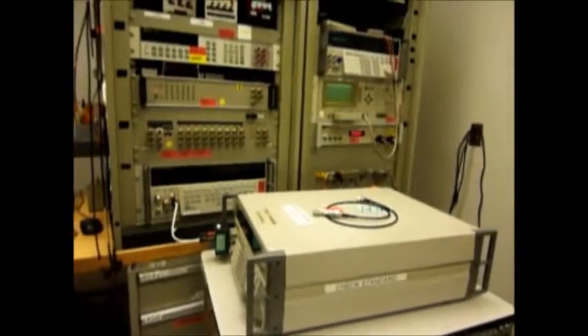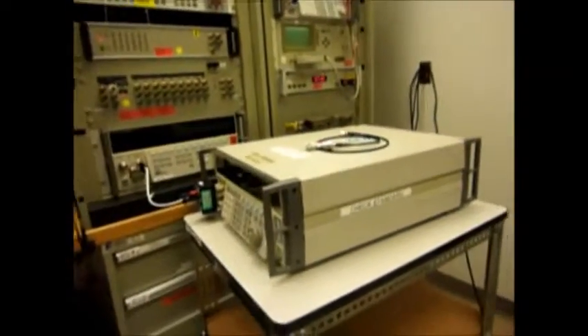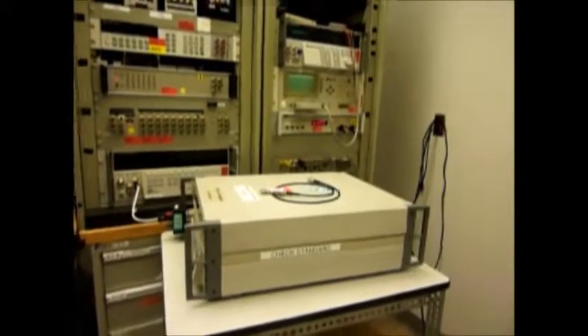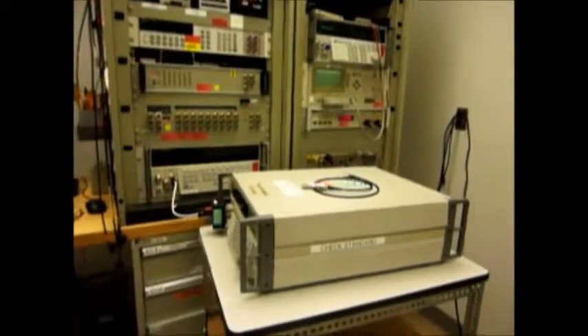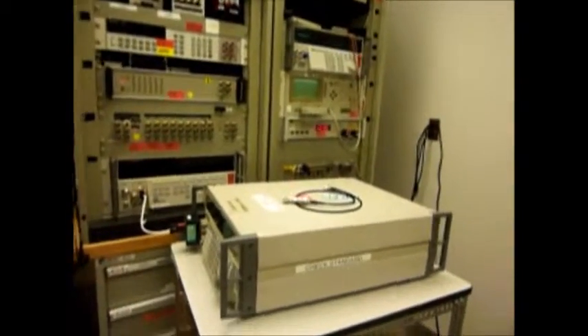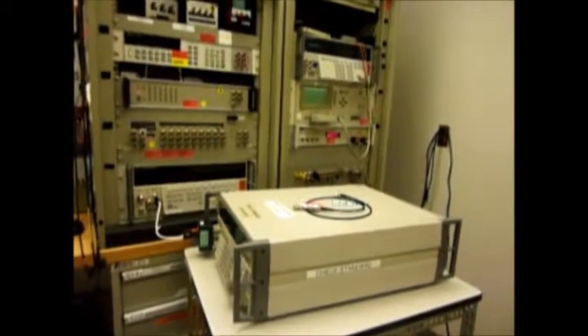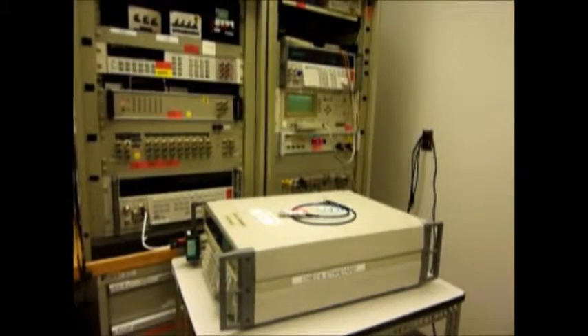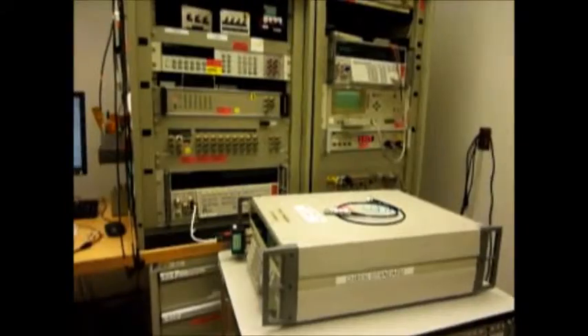So this calibrator that we're looking at, this check standard, will then be used to check and verify the calibration stations that are used to then calibrate your meters. Correct.